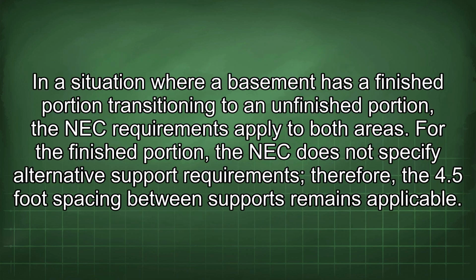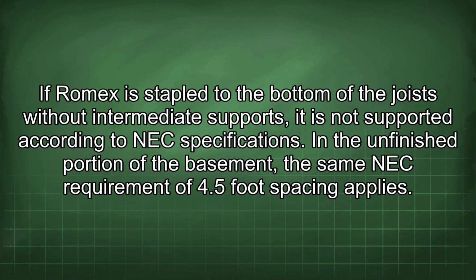In a situation where a basement has a finished portion transitioning to an unfinished portion, the NEC requirements apply to both areas. For the finished portion, the NEC does not specify alternative support requirements. Therefore, the 4.5-foot spacing between supports remains applicable. If Romex is stapled to the bottom of the joist without intermediate supports, it is not supported according to NEC specifications. In the unfinished portion of the basement, the same NEC requirement of 4.5-foot spacing applies.